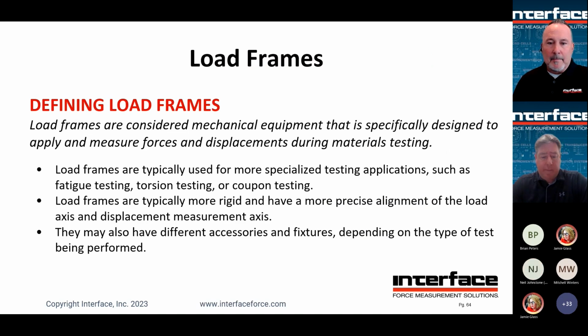All right, thanks Jeff. All right, so load frames - it's a little bit different than a test frame, right? We're considering a load frame essentially mechanical equipment that is specifically designed around a specific material test requirement. So typically it's going to be a specific tensile test, could be a torsion test, or it could be coupon testing.